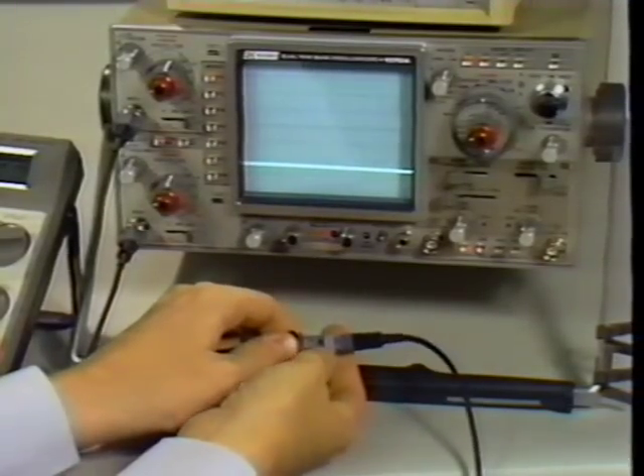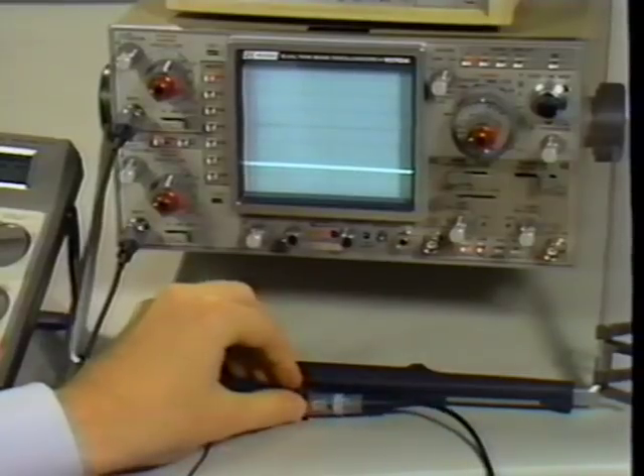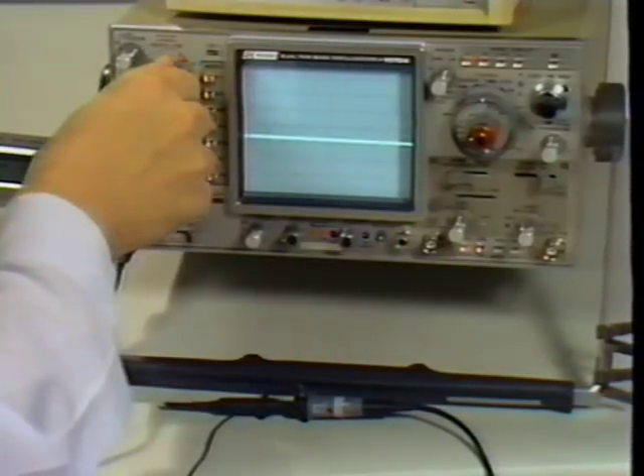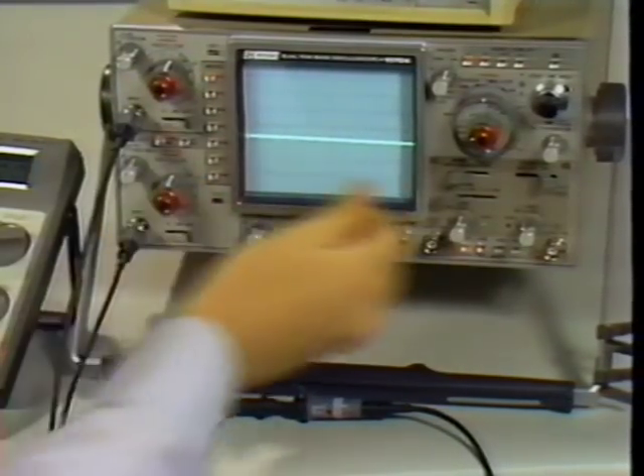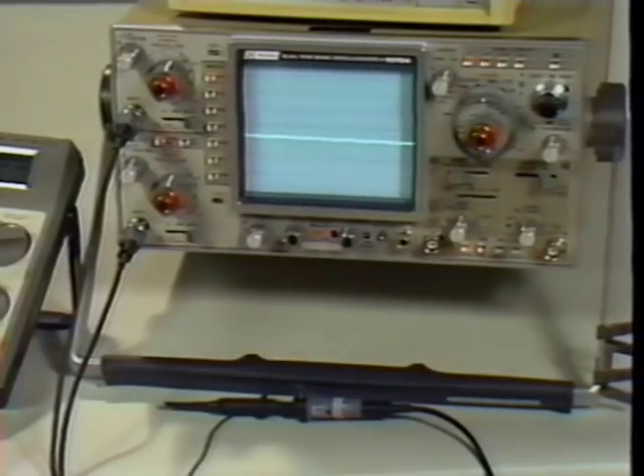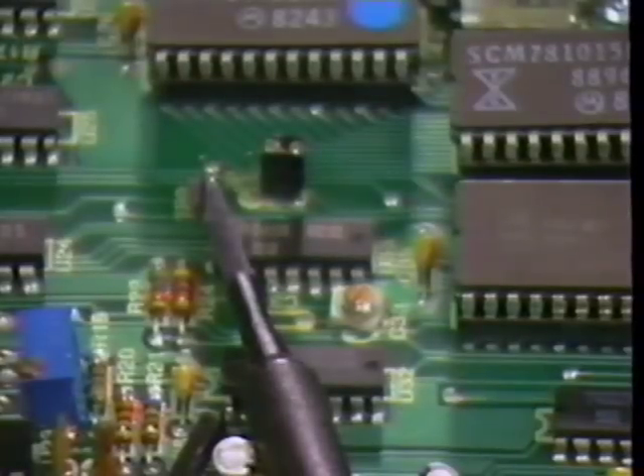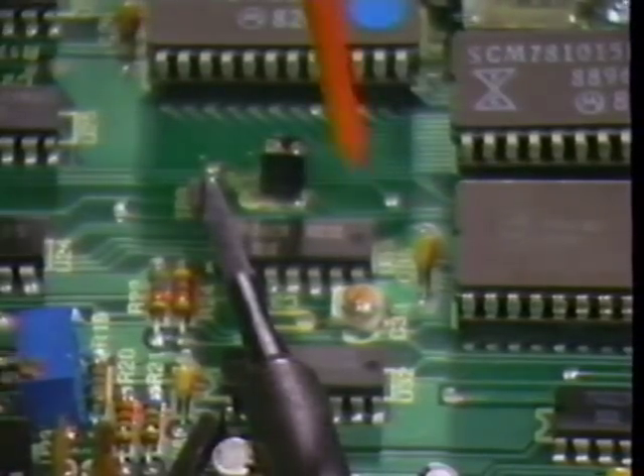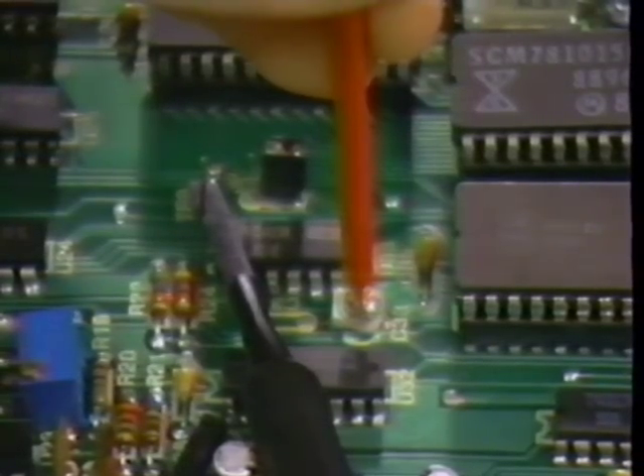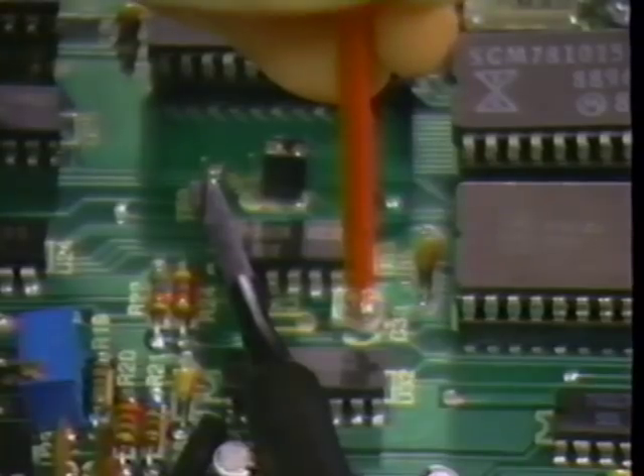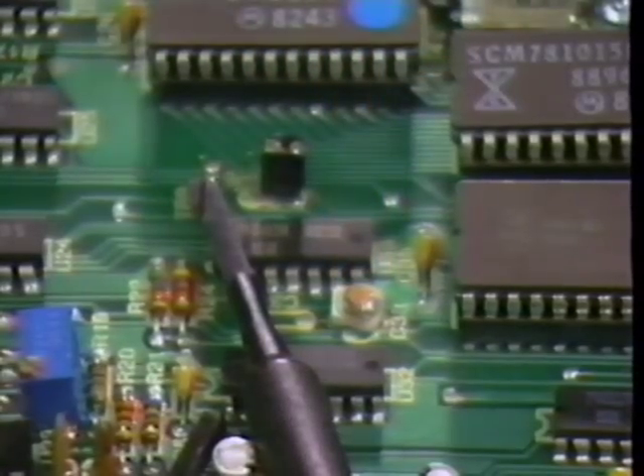Verify that your scope is set properly. Use ×10 probes DC coupled. Be sure that all calibrate knobs on the scope are in the locked position. Otherwise, the readings will be invalid. Adjust the variable capacitor for a stable 100 nanosecond square wave on channel A. Use a non-metallic alignment tool to prevent adding capacitance that might affect the alignment.